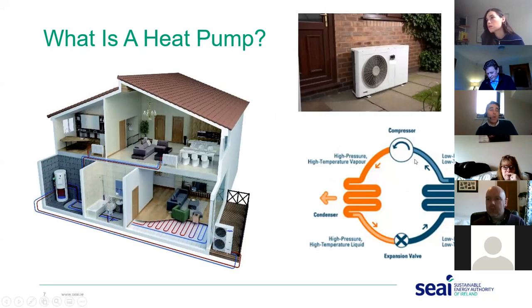Basically air is absorbed through the evaporator, and there's a refrigerant liquid within the evaporator section that has a very low boiling point. So this creates a low pressure, low temperature vapor. This goes through a compressor to increase the temperature even more, and this is what's brought into your hot water cylinder, say in a split system. This heats the water in your cylinder, and from the cylinder, then the underfloor heating and your rads are served.